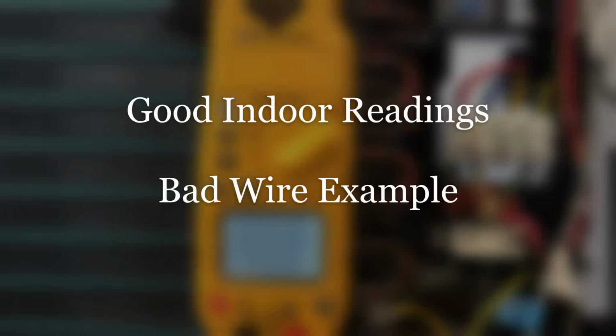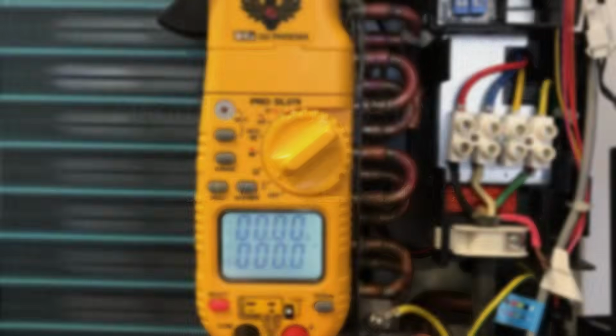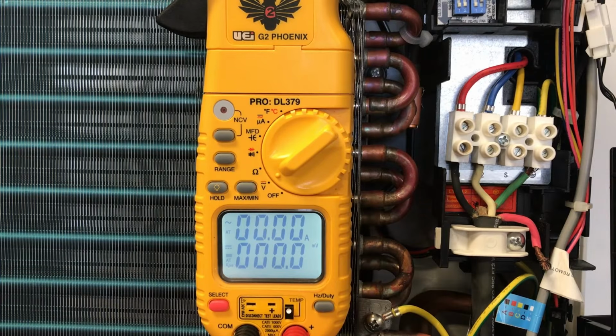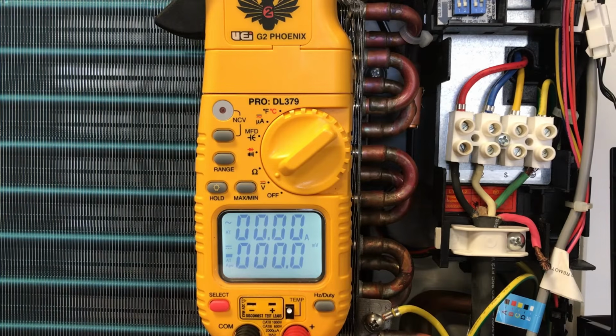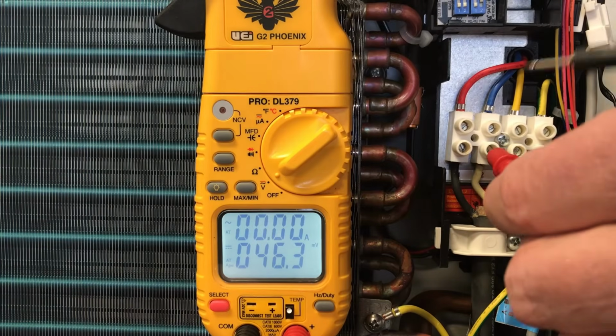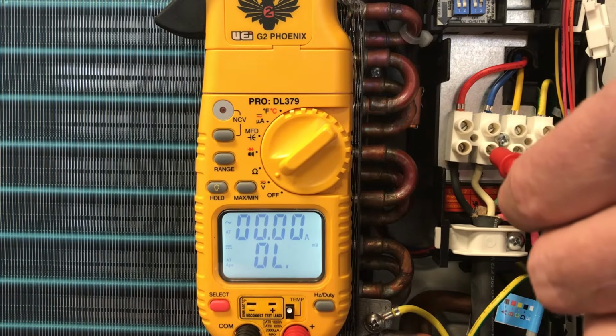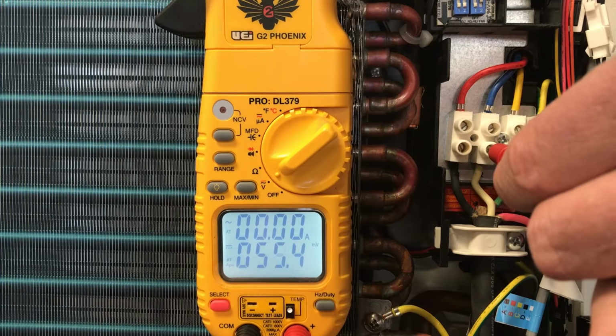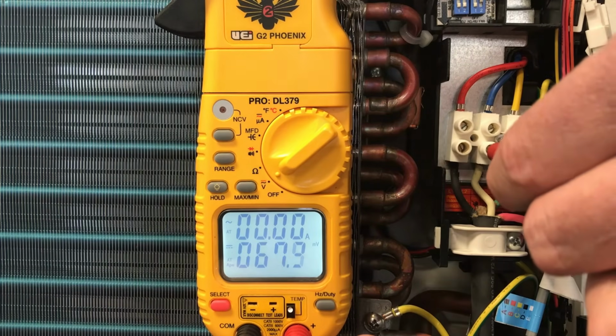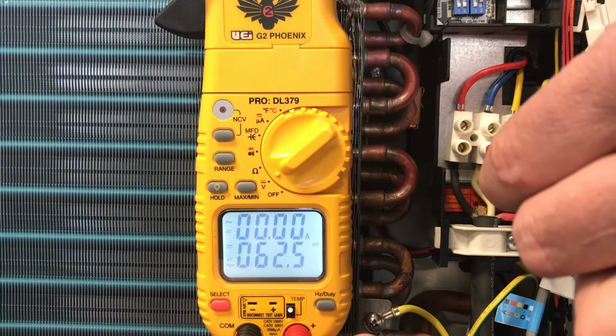All right, now we just showed you that we might have a problem with the indoor unit at the outdoor unit, so we've moved on to the indoor unit to show you what voltage you would get at the indoor unit. So we're going to check the same two terminals, the L2 and S. So our red is going to go on to L2, and our black is going to go on to our S. And outside we had a steady negative DC voltage.